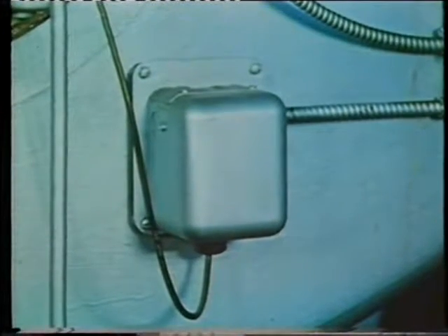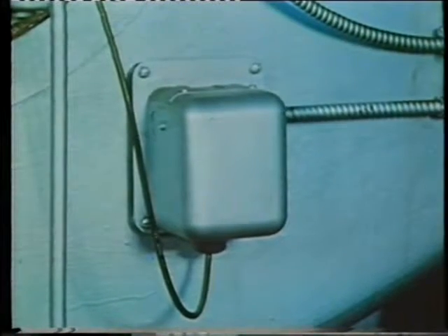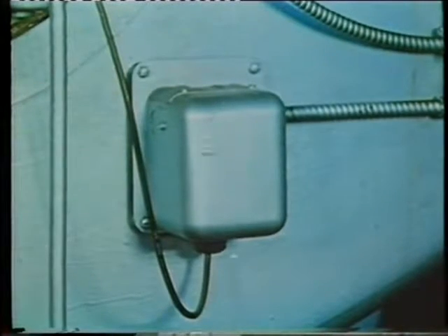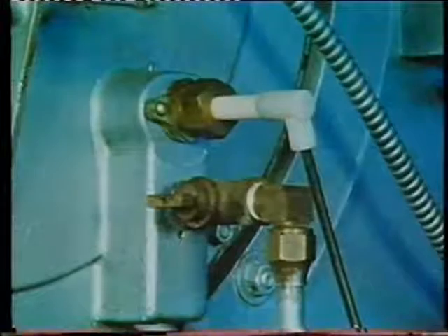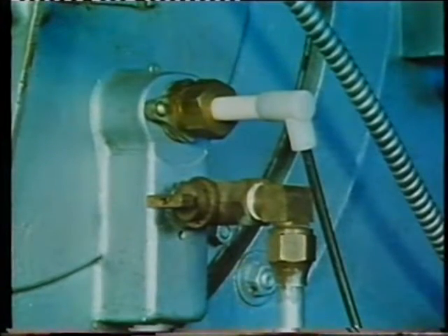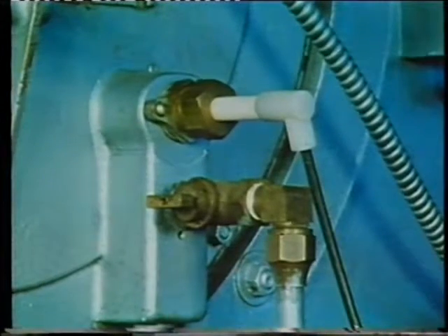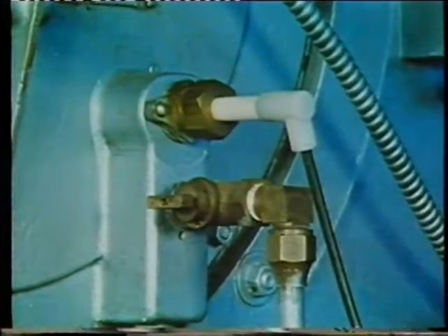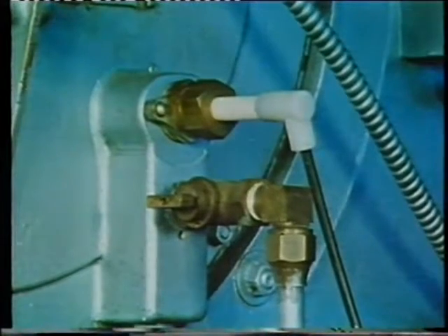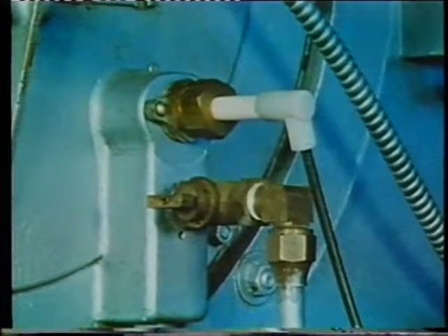The ignition transformer is energized at the same time as the pilot solenoid and produces a high voltage spark at the tips of the ignition electrode. At startup, the spark from the electrode ignites the pilot gas. The pilot flame is used to ignite the burner when the programmer calls for delivery of the air-oil mixture for main flame.